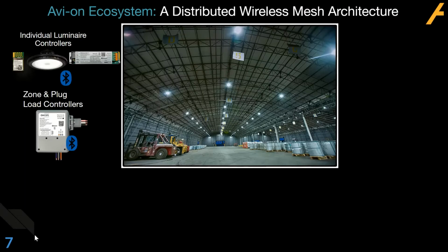We also have more traditional load controllers and plug load controllers for cases where we're trying to control a larger group of fixtures that all operate as one group, rather than being controlled individually. This is a 20 amp relay, actually 16 amp rated device, so you can put a full circuit of fixtures on this single device. 0 to 10 volt dimming is the standard protocol we use.